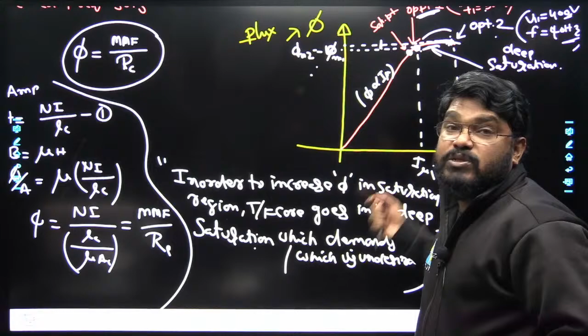If operated other than the rated frequency, that is, keeping applied voltage constant while frequency is reduced below its rated value, the operating point shifts. To increase the flux in the saturation region, the transformer core goes into deep saturation, which demands a very high amount of current from the source. That is example point C.